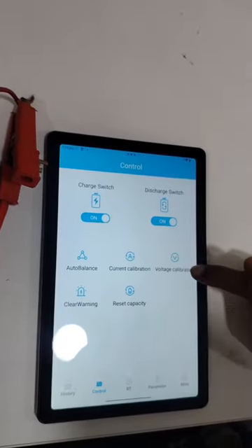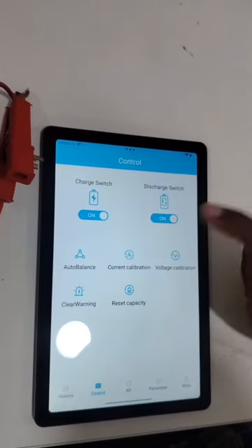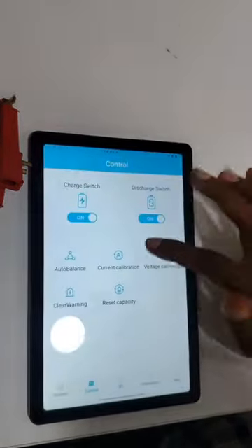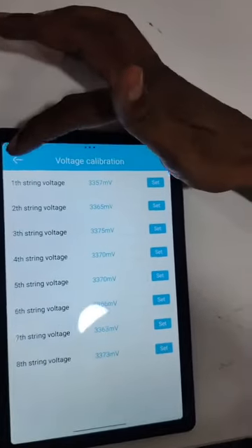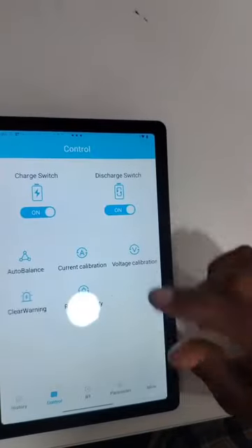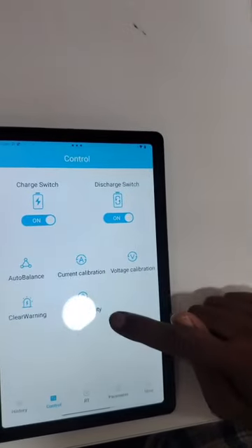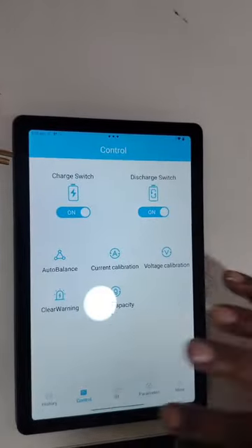Then we have current calibration and voltage calibration values. You can set the values here. Okay, so some Chinese values are written. So here you can set the values of actual current and voltage through this, and you can clear the warning as well as reset the capacity.